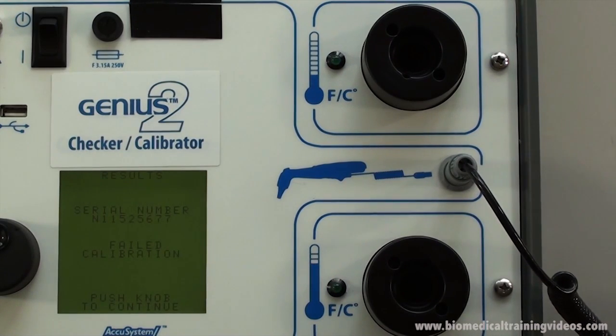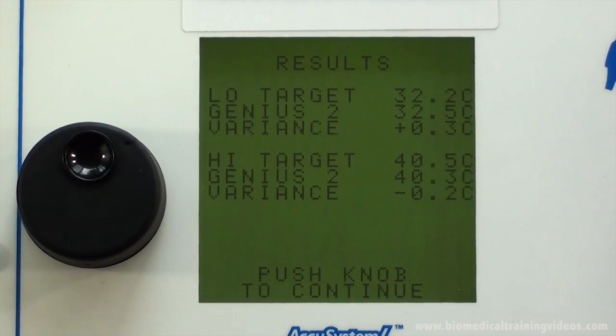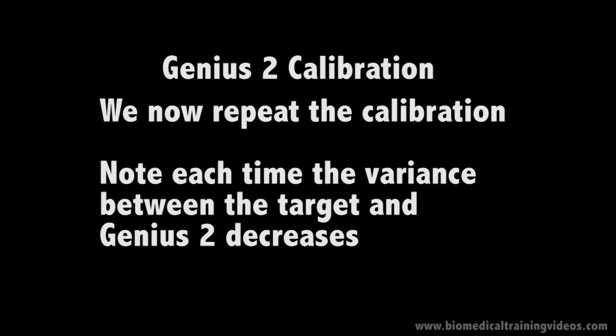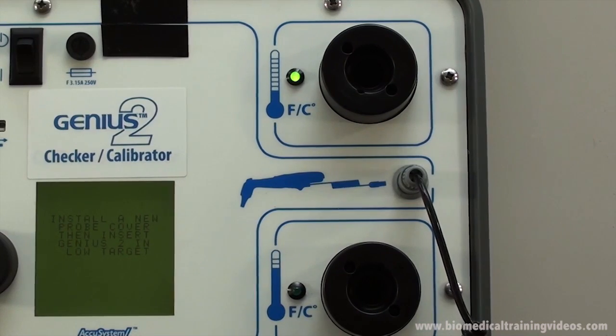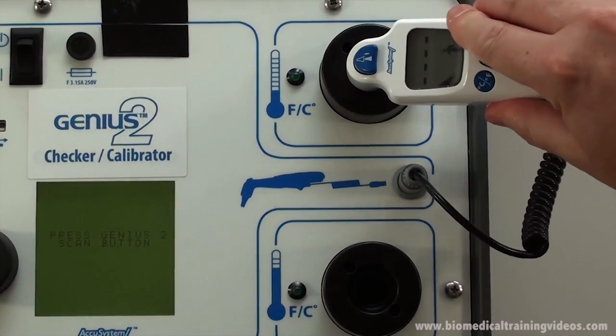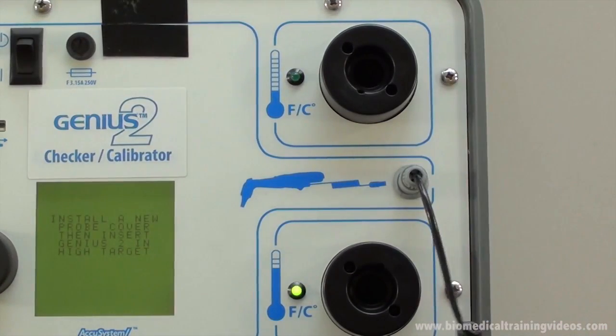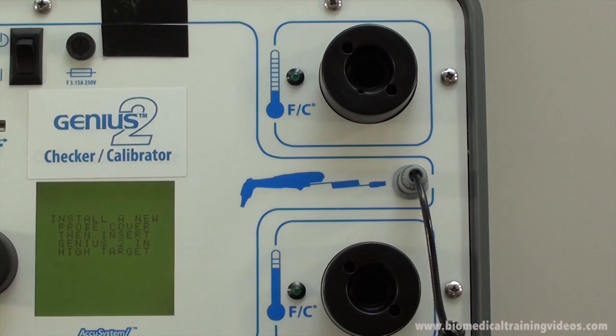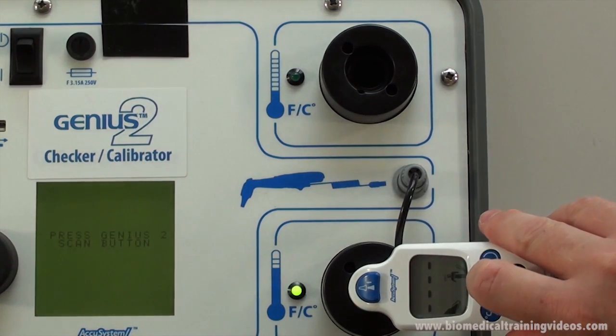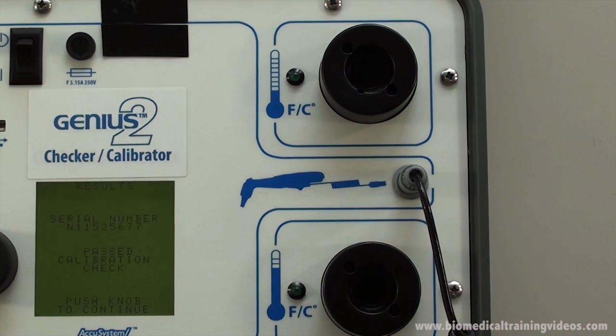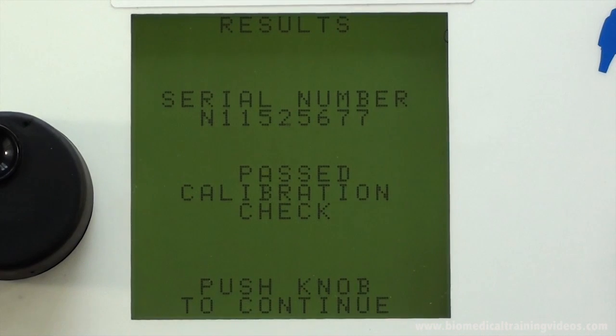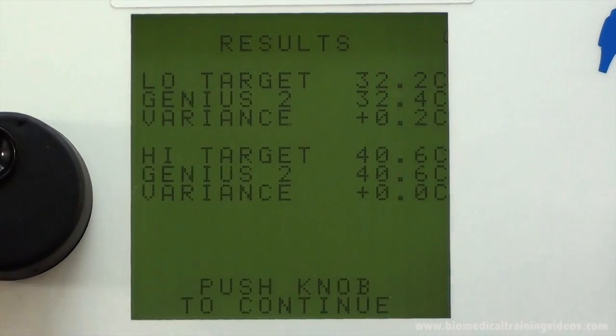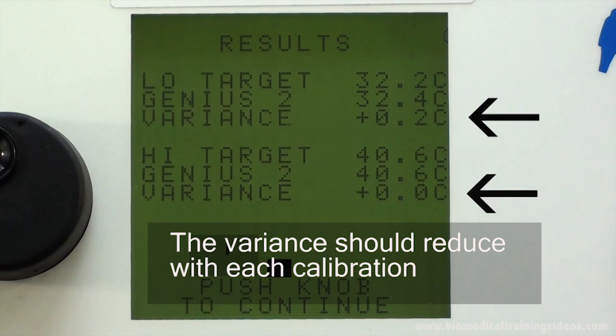And as you can see, we failed calibration. The difference between the target and the thermometer is too great, so we have to repeat. So each time you repeat the calibration, that variance will reduce, or ideally it will reduce. So again, going a second time now. And we've passed the calibration. And here again you can see the variance has reduced to almost 0, so it's acceptable.